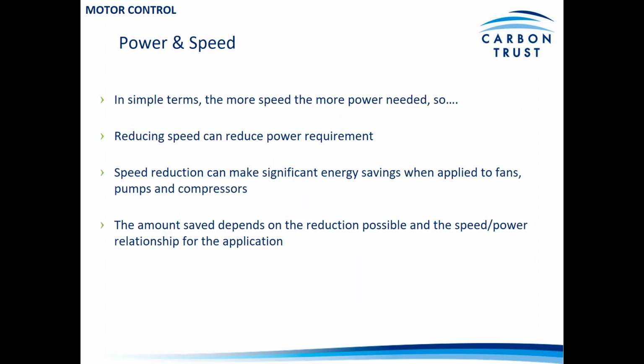So in simple terms, the more speed that's required, the more power that's needed. So if you can reduce the speed of your motor, that will reduce the power requirement. And that speed reduction can make significant energy savings, especially whenever it's applied to fans, to pumps, and to compressors. And the amount of saving that's available is dependent on the reduction that's possible through the speed and power relationship that we'll come on to shortly.